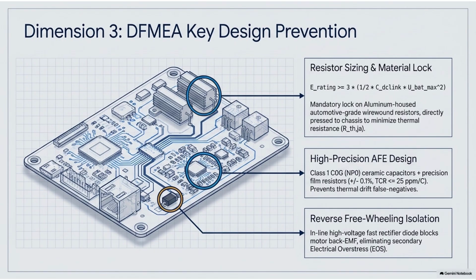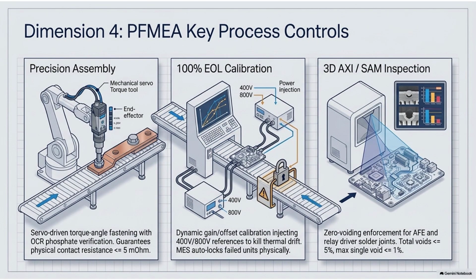It must be. Consider the high-voltage bus bars and the relay terminals inside the casing. These metal connections must seamlessly pass hundreds of amps of current. If a bolt holding two copper bus bars together is even marginally loose, the microscopic physical contact area between the metal plates is vastly reduced. This creates tiny gaps, which dramatically increases the physical contact resistance at the joint. And as we learned with Joule heating at the beginning, resistance multiplied by massive current equals massive heat.